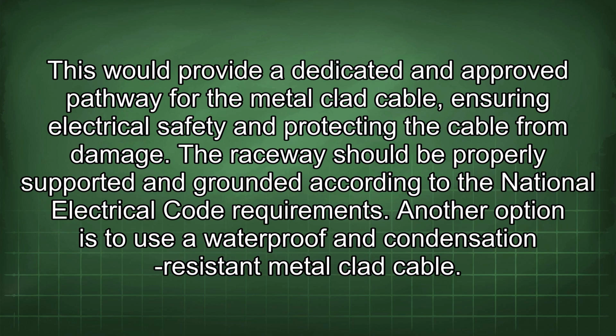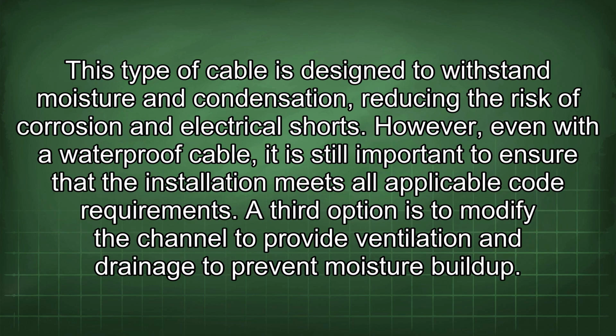Another option is to use a waterproof and condensation-resistant metal-clad cable. This type of cable is designed to withstand moisture and condensation, reducing the risk of corrosion and electrical shorts. However, even with a waterproof cable, it is still important to ensure that the installation meets all applicable code requirements.